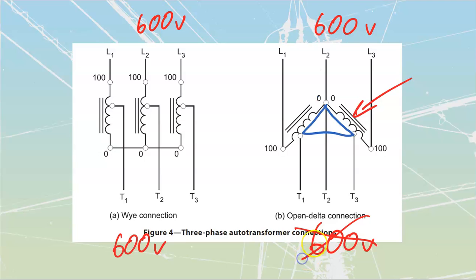So we'll just quickly clear that right now. I will say that this motor would be starting at 390 volts, and then when I complete my connection and I take out the actual autotransformer and go to my full line running, then it would go to 600. So it starts at 390 and then runs at 600 if I'm using 65% taps.